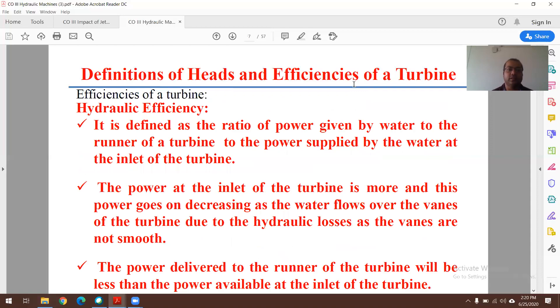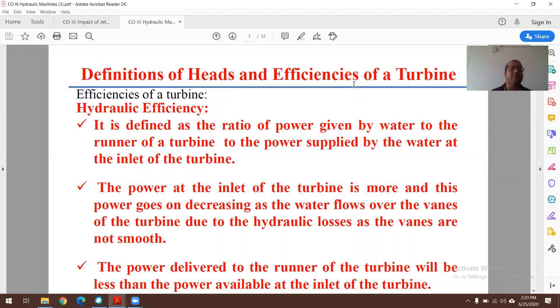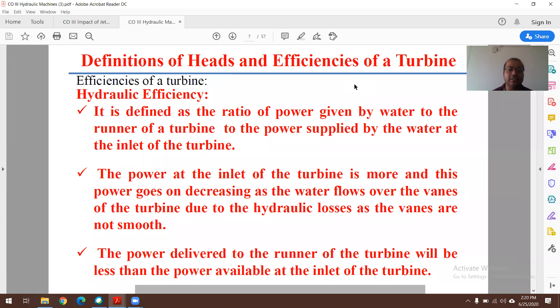Hydraulic efficiency is defined as the ratio of power delivered by water to the runner of a turbine to the power supplied by water at the inlet of the turbine — essentially output power divided by input power, multiplied by 100 for percentage. The power at the inlet is more, and it decreases as water flows over the vanes due to hydraulic losses, since the vanes are not perfectly smooth. Therefore efficiency is always less than 100%, ranging from 0 to 1 in decimal form.